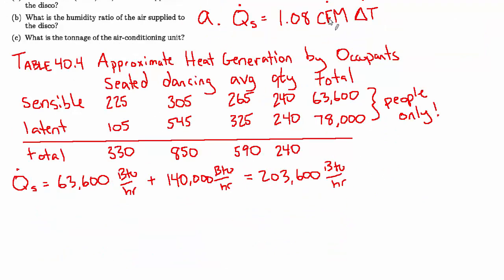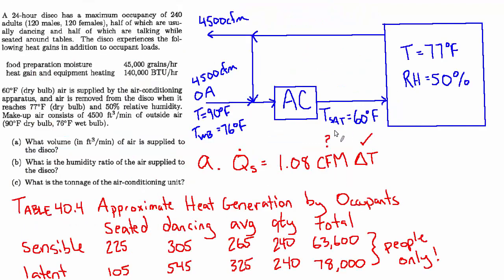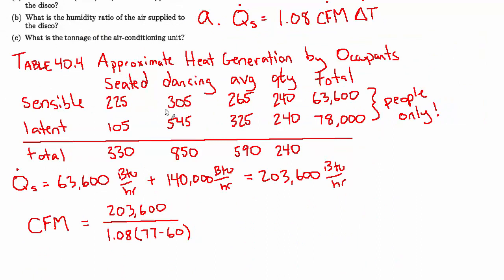Which we can then plug into this formula, which I'll rearrange to solve for CFM. So the volume flow rate of air that we need is going to be q dot over 1.08 and the Delta T. So let's sub right in: 203,600 over 1.08 and 77 minus 60, where 77 is the conditions in the room and 60 is the temperature of the supply air. And that works out to 11,090 CFM, and that is answer A.